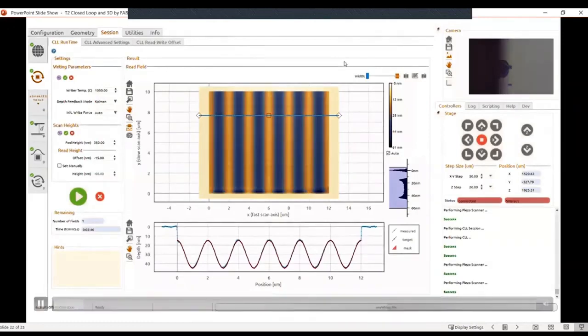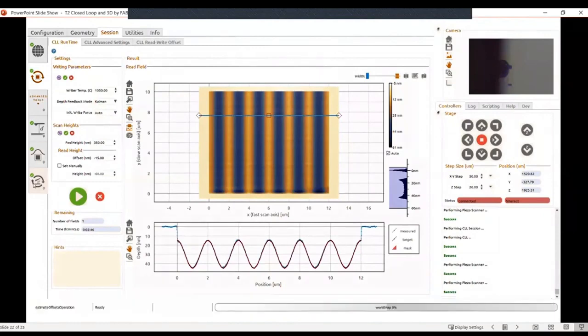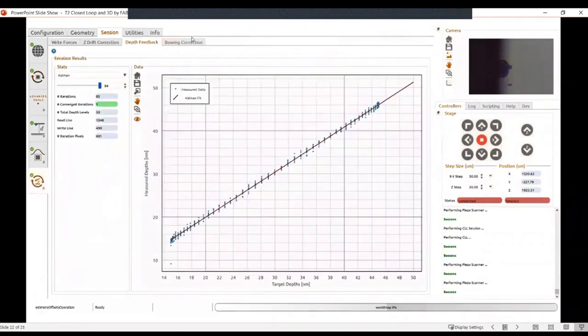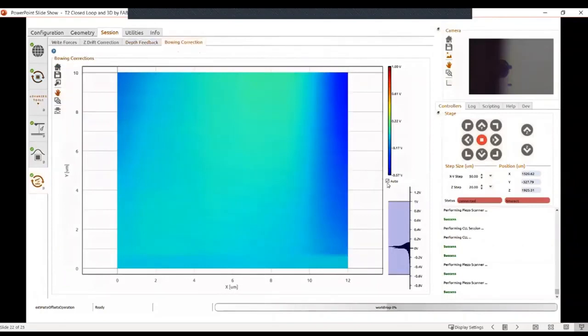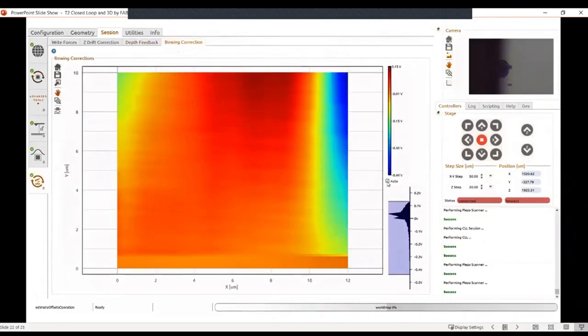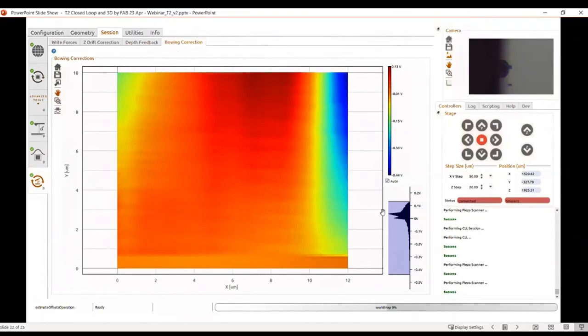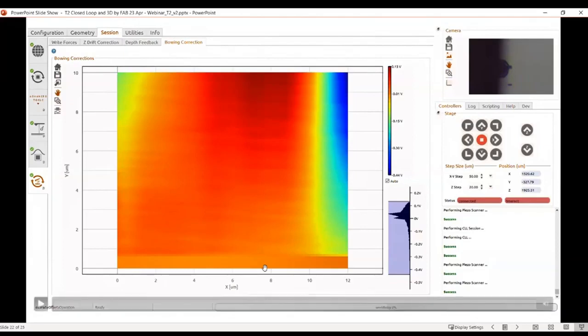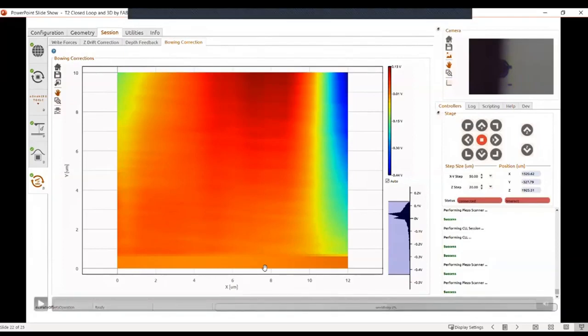And I can quickly show you. So when we go into our analytics tab, we can see a map of the voltage correction that was applied on our force voltage. And you can see that, just as expected, we needed to do some corrections, especially towards the edges, and especially when we have already written a lot of the area. Because as you can imagine, the more pattern we write, the more we change the capacitance and the more severe the effect gets. But we have corrected that. And as you could see, the result was rather good.